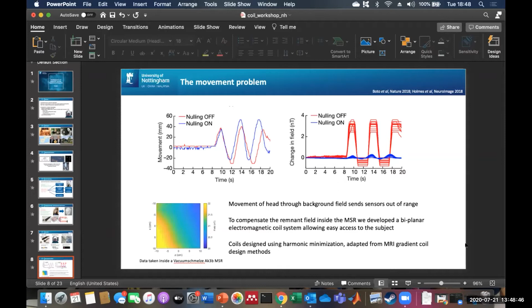So what we decided we needed to do was to compensate the remnant field inside the shielded room by developing an electromagnetic coil system which allowed easy access to the subject. You could imagine just putting Helmholtz coils around some sort of cage, but we want to be able to get in and out. We want the person inside the experiment to feel comfortable, and we went for a biplanar coil system, designed the coils using harmonic minimization, and as mentioned before, in Nottingham there's some great expertise in MRI gradient coil design, so we adapted an MRI gradient coil design method to do this.